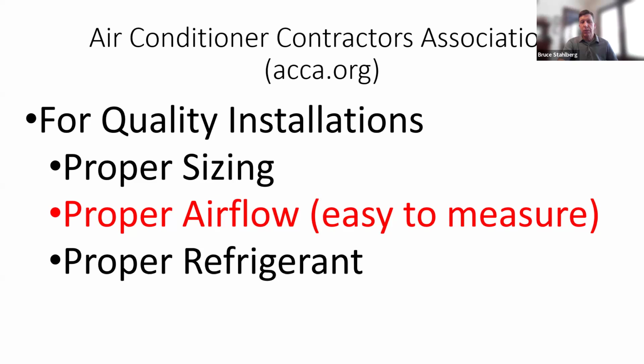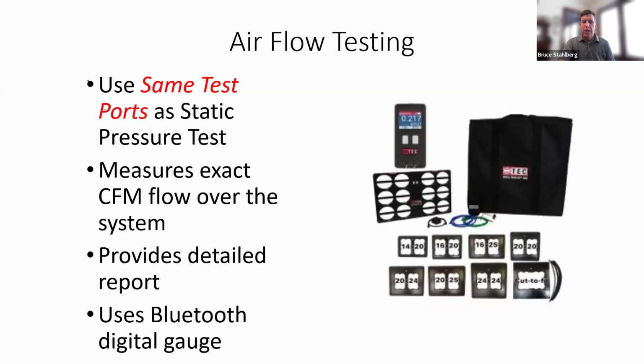Okay, now the things that we're looking for with our quality install is the proper sizing. We talked about that. Proper airflow, which is actually very easy to measure, and proper refrigerant, which as a technician, I don't have the ability to measure that. That's more of an HVAC technician. But airflow testing uses the exact same test ports that we talked about with static pressure. Now, if you want to just get started, I think it's a good idea just to measure static pressures. But if you happen to have this tool, you can take another 3 or 4 minutes and get an airflow, which is really a critical thing to do. Especially when we're installing something new, airflow is really an important thing that we do not measure currently.